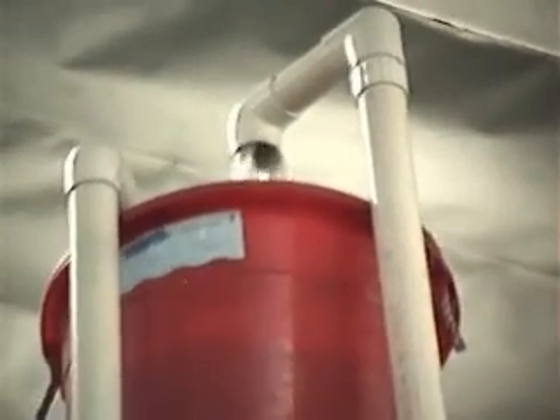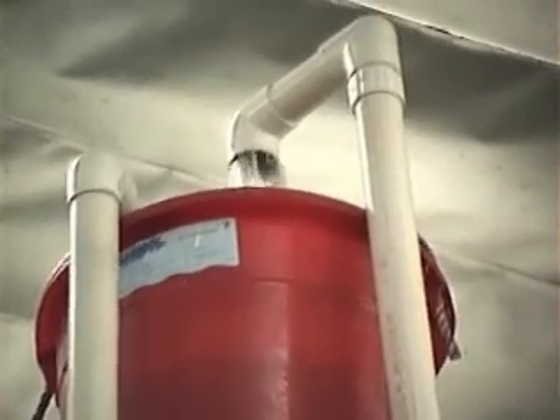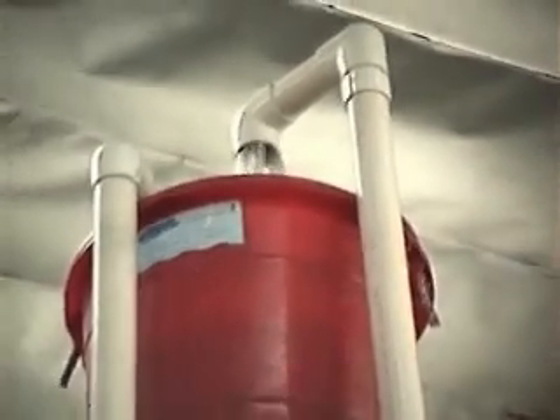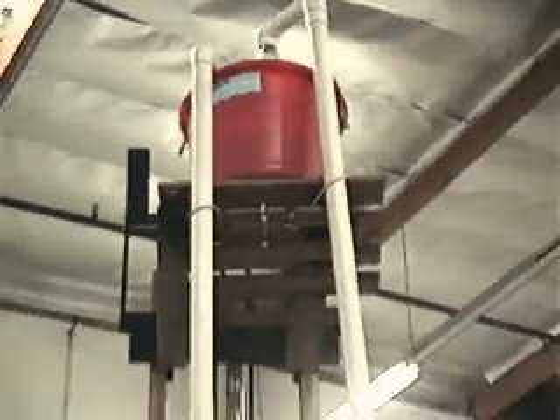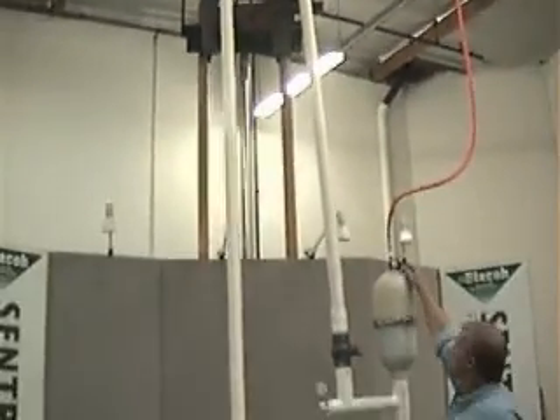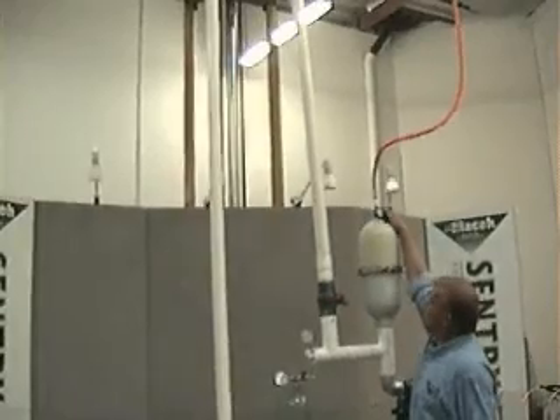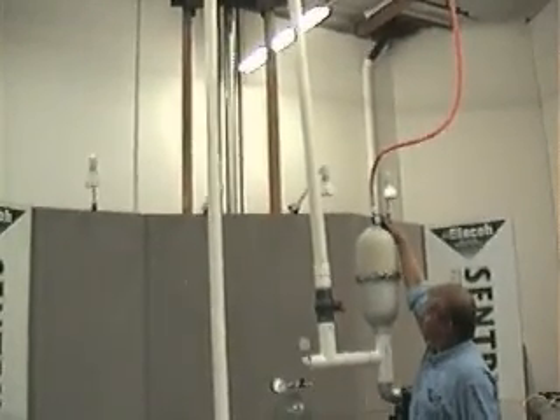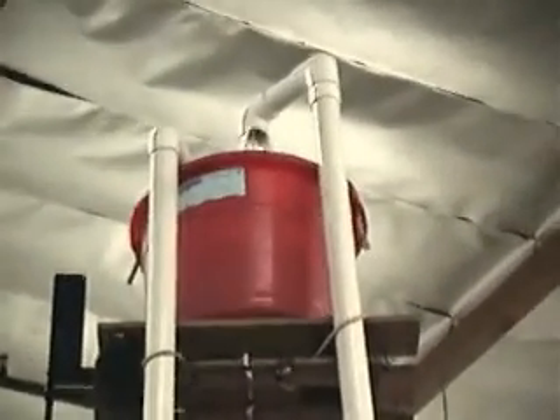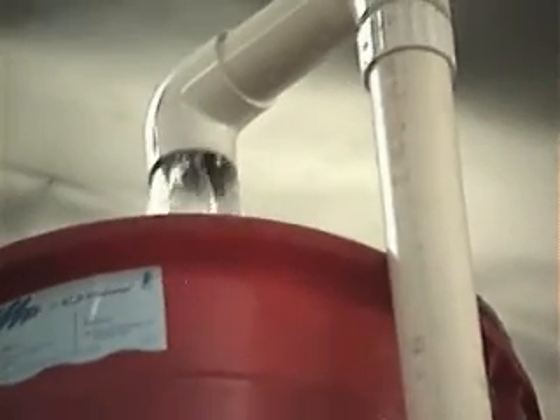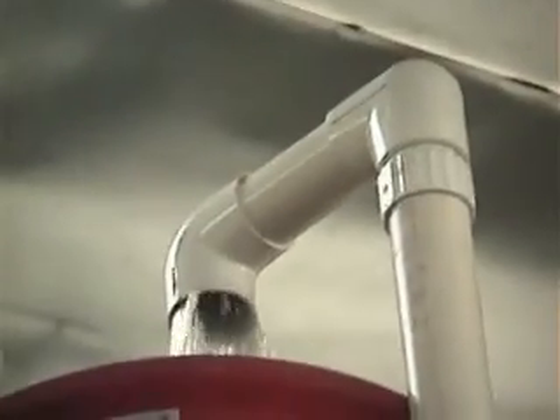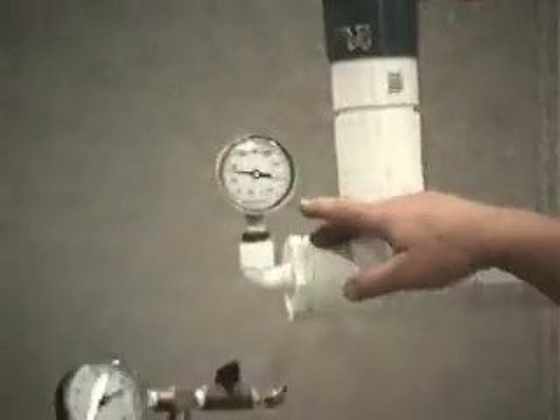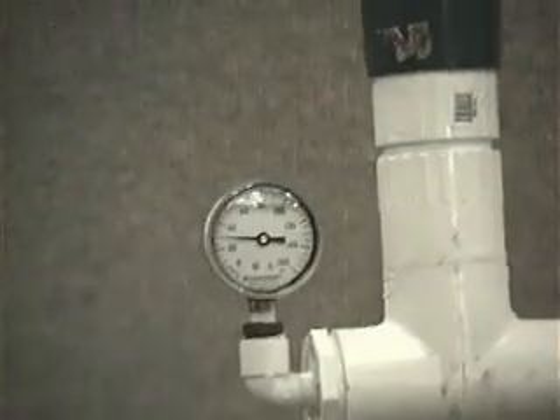As I dial in the pulsation dampener, you'll see the discharge pipe stop vibrating. You'll start to see a continuous flow at the discharge. And you'll see that the pressure gauge on the discharge is barely moving. We've now tuned in the discharge side of the pump.